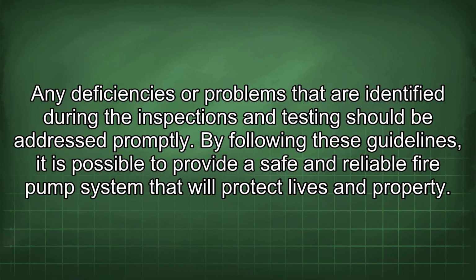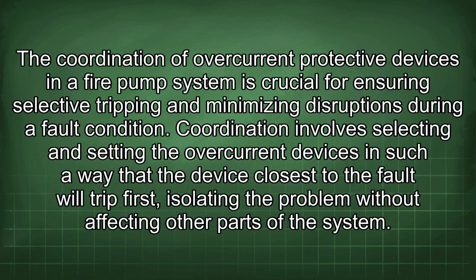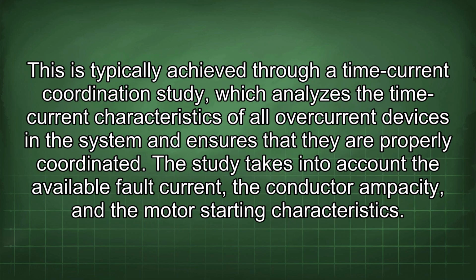The coordination of overcurrent protective devices in a fire pump system is crucial for ensuring selective tripping and minimizing disruptions during a fault condition. Coordination involves selecting and setting the overcurrent devices in such a way that the device closest to the fault will trip first, isolating the problem without affecting other parts of the system. This is typically achieved through a time current coordination study, which analyzes the time current characteristics of all overcurrent devices in the system and ensures that they are properly coordinated.